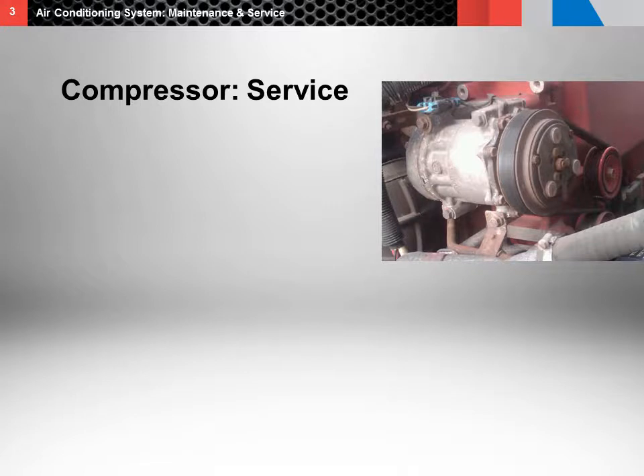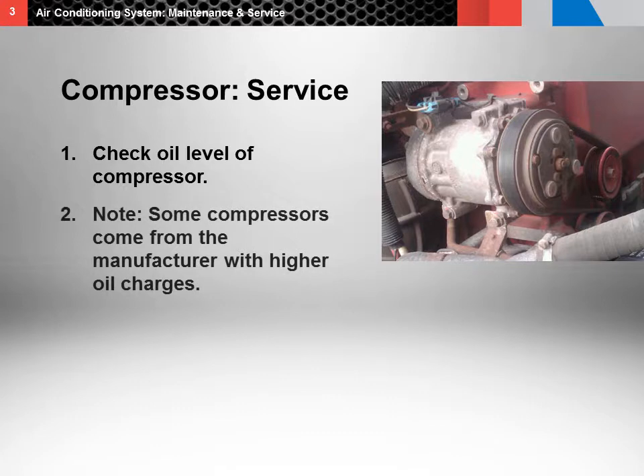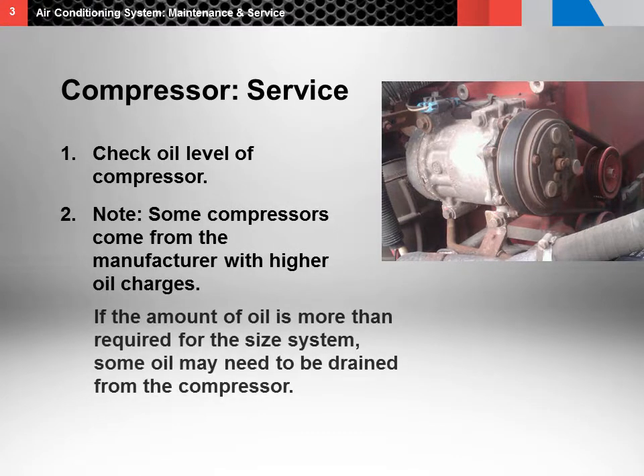The first place to start servicing and maintaining the compressor unit is oil level. Anytime the air conditioning system has a part removed, the compressor oil level must be checked. Be aware that some compressors come from their manufacturer with higher oil charges than others. So if the amount of oil is more than required for the size of system you're servicing, you may have to drain some oil from the compressor.